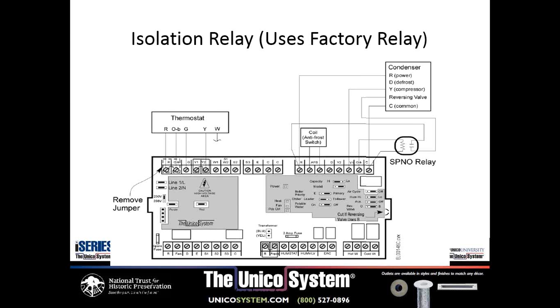And you need to check with your manufacturer, but some brands, particularly Carrier and Bryant, have heat pump units that require a factory isolation relay, because sometimes they can get false signals on defrost. But again, this is covered in our Bulletin 30-39, which is our installation manual.